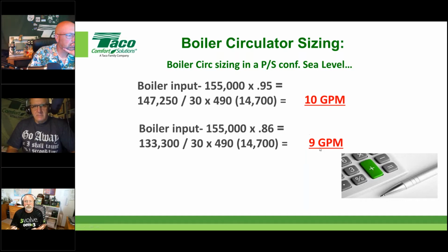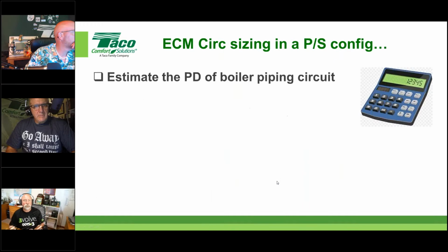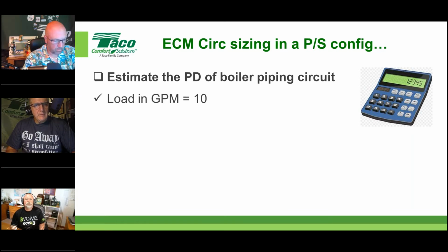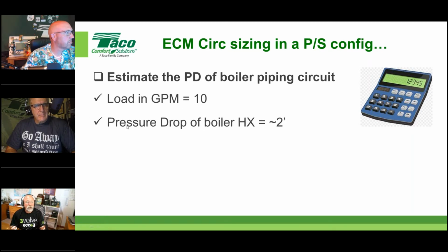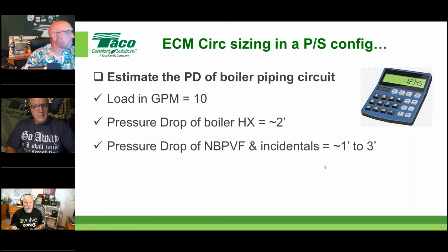That's all I need. So your GPM is always going to be based on what the boiler can do at the specific job you've got it on. So you have to take this stuff into consideration, okay? Otherwise, it leads to oversizing. We already showed you what that does. So to estimate the pressure drop of the boiler circuit, let's always start with the load. In this case, our load is 10 GPM. I'm going to figure out from the boiler manufacturer's information what the resultant pressure drop is at that given flow. In this case, it's around 2 feet of head. Even if I add my own pipe, incidental valves and fittings, I'm at as little as less than 1 foot, or maybe as high as 3, depending on what components you have in that little circuit.